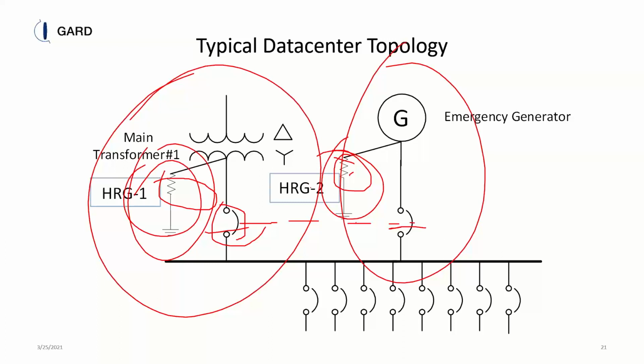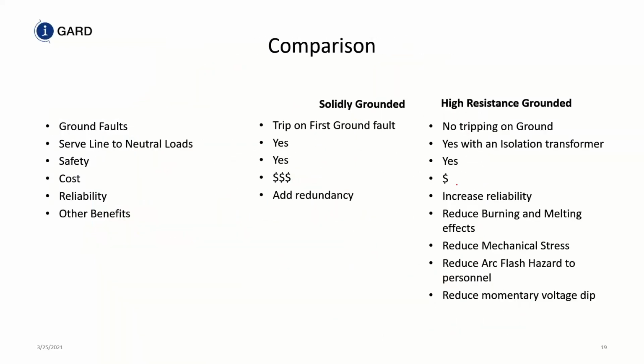Next question. Comparing two grounding systems, solidly grounding is more expensive than high resistance grounding system. But my understanding is high resistance grounding systems need isolation transformer and resistor, while solidly grounded only needs a bonding wire, which is number 6 AWG, right? Well, if you're getting your system from the utility and you don't have your own transformer that's feeding your plant, then yes, solidly grounded system is probably the only thing you can do.